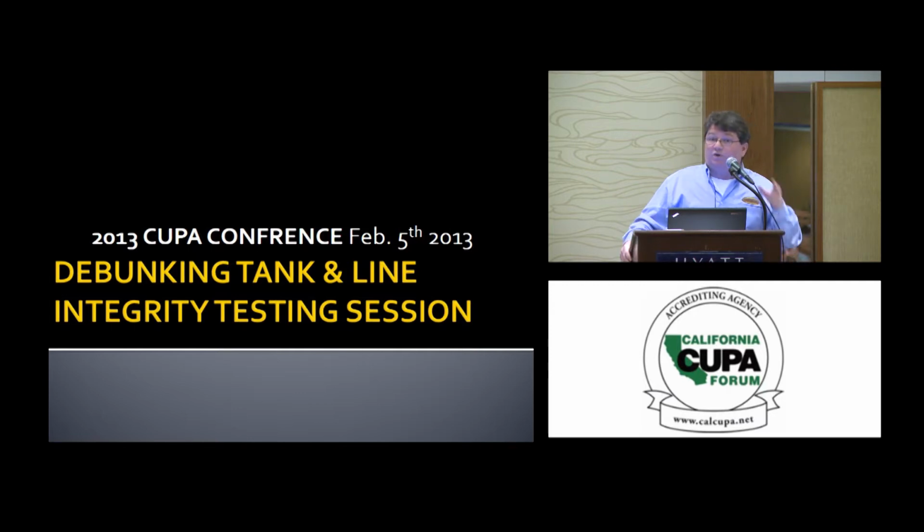You're running the triangle, you're running the full hazmat materials. You're in there because it's not a safe environment. Truck stops are pushing fuel like there's nobody's business. Some of them do 5 million gallons a month. Do you know that Warren Rogers, I believe, is certified for 2.2 million, some number close to that? So that means our best SIR in the country is 2.2 million, and he's doing 5 million a month. We have over 130 stations in America that do over 5 million a month in diesel. That's where tank testing's needed.